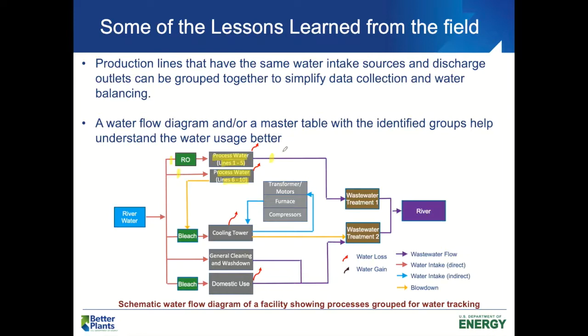Another lesson is with respect to the lack of metering and submetering in place for system-level water usages. Typically what we find in the field is that a permanent submeter is not in place for system water usage. One way you could work around it is by using short-term monitoring, like non-intrusive ultrasonic flow meters, to data log system water usages and extrapolate it for annual consumption.